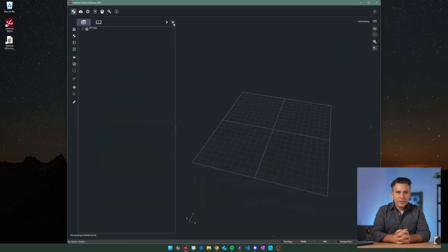First, expand the project tree and double-click on the session you want to work in. This will take you straight to the Session tab. Quick note, if you plan on measuring a couch axis dataset to determine how close it is to your physical isocenter, make sure to measure the couch axis dataset first. You can't measure the iMarc before the couch. To see how to create and measure a couch axis dataset, check out the video linked in the description below.